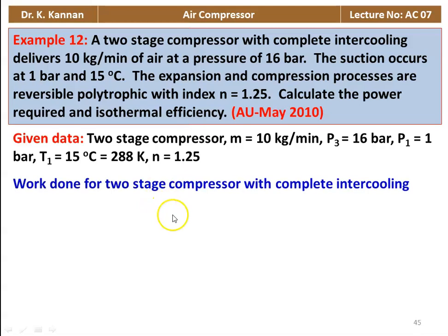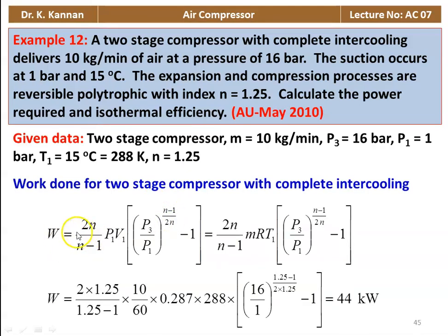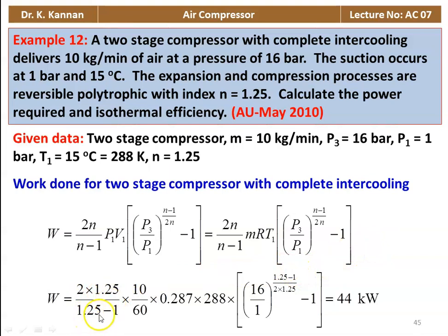Work done for a two-stage compressor with complete intercooling: W = [2n/(n−1)] × P1V1 × [(P3/P1)^((n−1)/2n) − 1]. Since P1V1 = MRT1, substituting: W = [2 × 1.25 / 0.25] × (10/60) × 0.287 × 288 × [(16/1)^((0.25)/(2×1.25)) − 1] = 44 kilowatts.